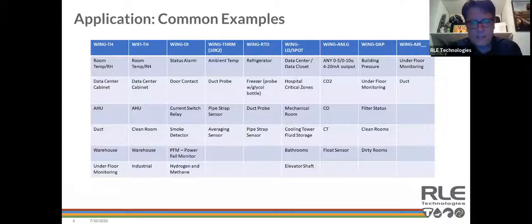We've actually successfully put a self-powered CT on the analog transmitter, so we've basically got wireless energy management strapped on anywhere to give you the data you want. An industrial plant I was just working with leveraged the analog with a float sensor. They've got these big tanks, and when it gets below a certain point, they need to know about it so they can trigger an alarm. So a lot of good use case examples for that.